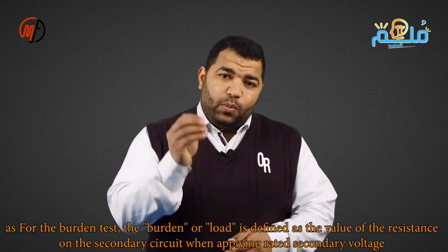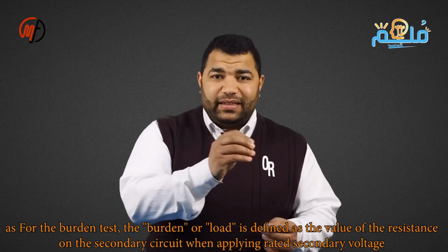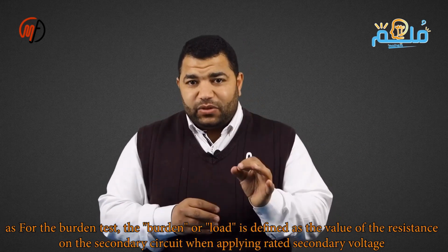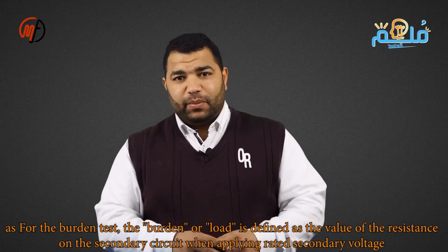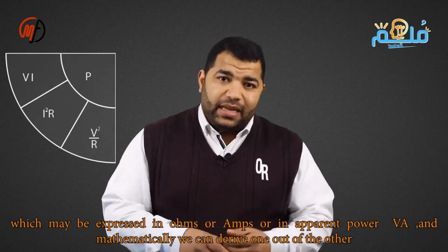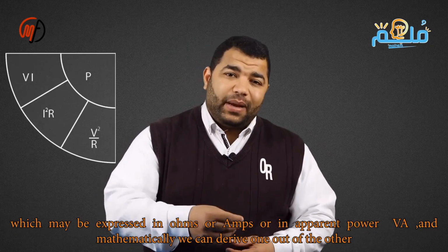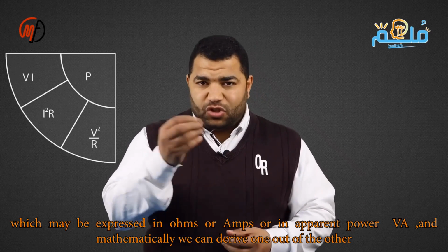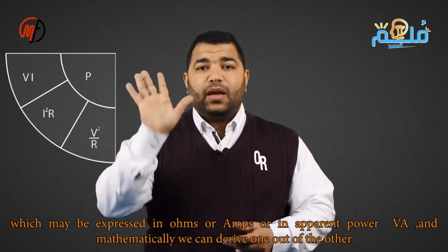To perform the test, open the terminal block at the first point in the secondary circuit, apply the rated secondary voltage through an ammeter to the relay devices, multiply the voltage by the ammeter reading to get the burden in volt amperes, and compare this with the nameplate burden value, which should be equal or less. This ensures the VT operates correctly.